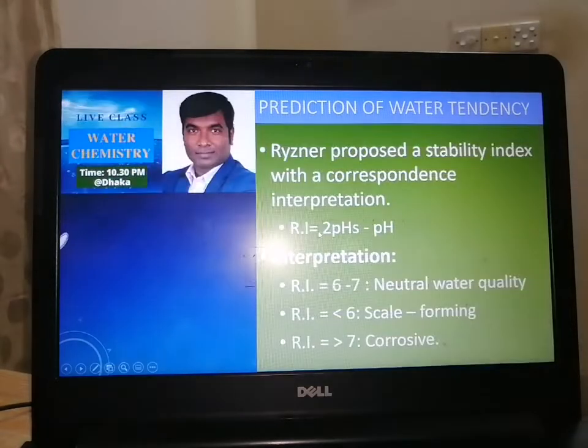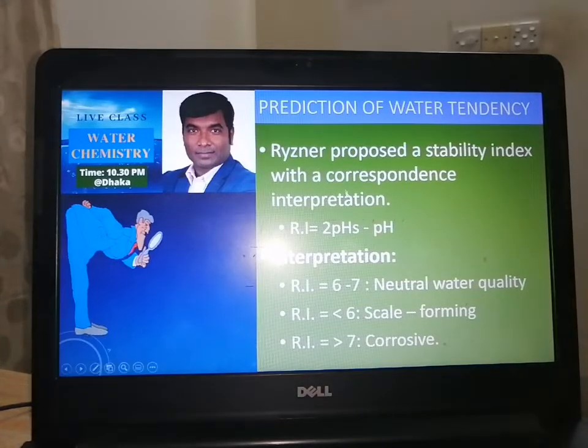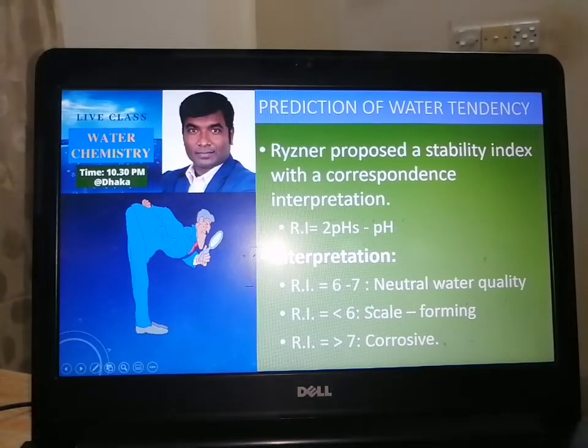This is not a very extensive index, but we have another one called the Ryznar Stability Index. We can calculate the Ryznar index, and if it is 6 to 7, we say the water is okay, the water is good. If the RSI is less than 6, the scaling chance is very high. And if it is above 7, the more it goes toward 8, 9, 10, the more corrosive it will be. So it depends on the COC and on the practical limit.